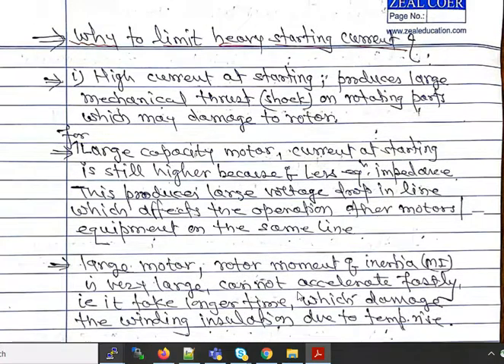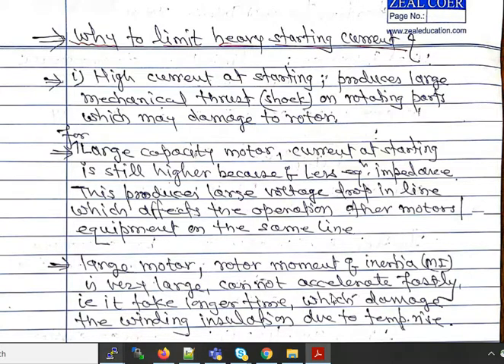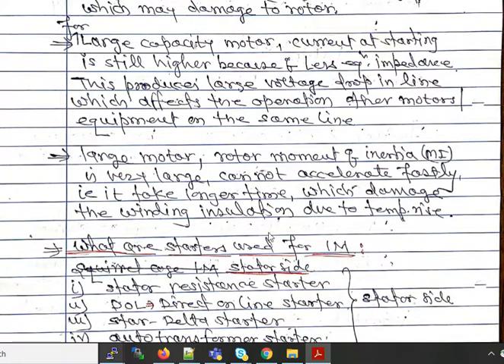Why must we limit the heavy starting current? High starting current produces large mechanical thrust on the rotating parts of the motor, which may damage the rotor and shaft. For large capacity motors, the starting current is even higher due to less equivalent impedance, producing large voltage drops in the lines — increasing voltage regulation and affecting other motors or equipment on the same line. Also, large motors have high rotor moment of inertia, so they take a longer time to accelerate, which may damage winding insulation due to high temperature rise.